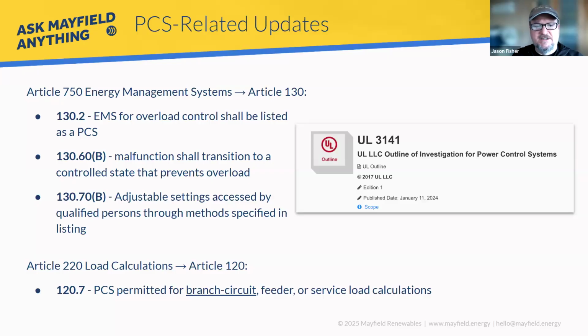It's a major change. It's actually been in place since 2020 in 705.13. We're technically in the third cycle now, but this is the second cycle where it's been source- or load-agnostic. That's the only thing the NEC says about PCS — otherwise, you just install the PCS, use general wiring requirements, and follow the instructions. But you should understand that you could list a PCS to do all kinds of other stuff which isn't NEC.